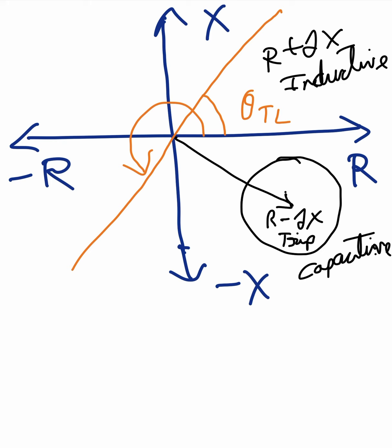When the generator loses its excitation, the locus of the equivalent generator impedance moves from the first quadrant to the fourth quadrant. The relay then trips the field breaker, and the generator is disconnected from the system. So this is basically the generator rotor protection for loss of excitation.